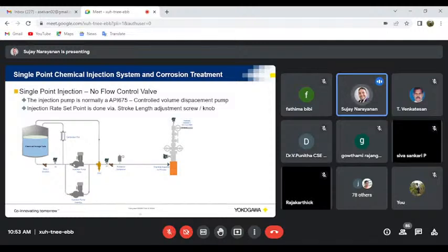Now, how this pump works is, it takes pockets of liquid for every stroke. It is like a piston, moving left, right or up, down. For every stroke of the piston, let's say it takes 1 ml of liquid. So if it makes 100 strokes, how much will it take? 100 ml. So for every stroke, the volume is metered in this pump. Clear? So if you adjust the stroke rate of the pump, you can adjust the volume pushed by the pump.